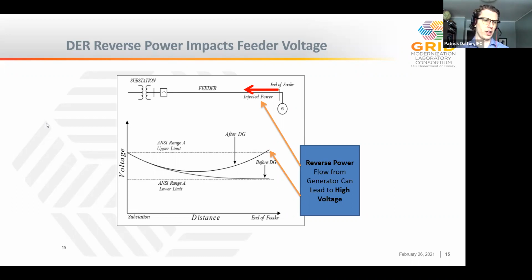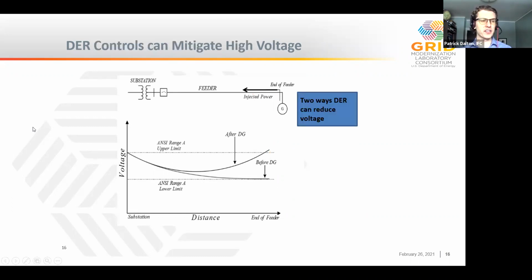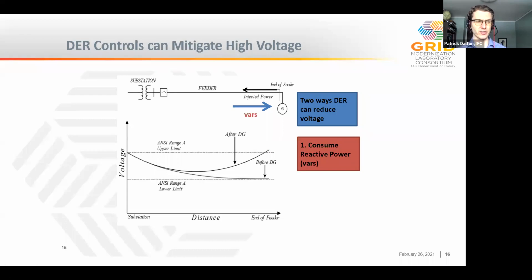So there are really two main ways the DER can help manage voltage. The first is consuming reactive power. There's a component of power called reactive power, or VARs, which is the unit it's measured in. If a DER is consuming that type of power to counteract the effects of the watts it's injecting into the system, that can have a meaningful impact — and that's the basis of the smart inverter functions at a fundamental level.